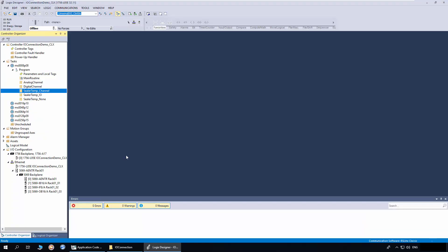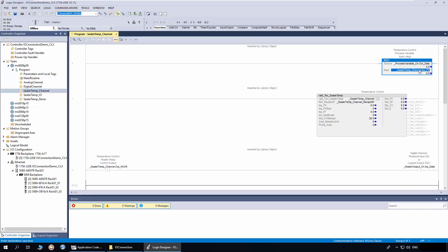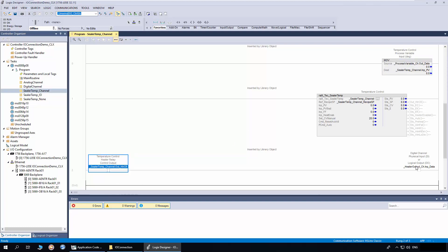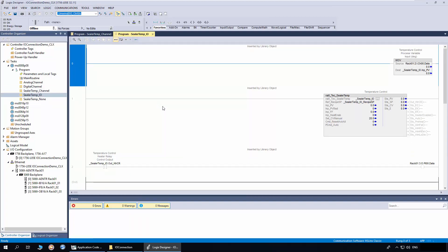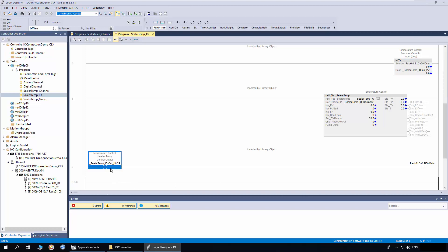I have opened the Logix file generated from the ACM project. First I will open the Sealer Temp Channel routine. You can see the process variable input is mapped to the analog channel out data. The heater control output is mapped to the digital channel input data. Next I will open the Sealer Temp I.O. routine. Here you can see the process variable input is mapped to the Channel 0 data of the analog input module, and the heater control output is mapped to the zeroth output of the digital output module.